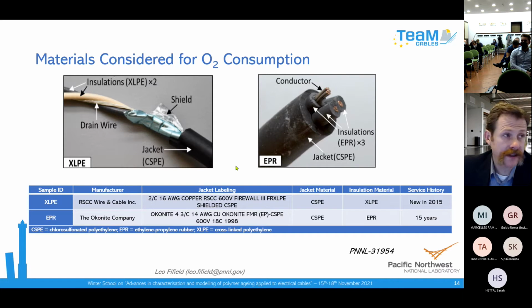In one case we also looked at what we call the dehydrochlorination index, since in chlorinated polymers it's the chlorine leaving that gives a good FTIR signal, compared to the carbonyl index for oxidation. But we haven't done a lot of research with PVC. The problem is that for PVC, conventional non-destructive techniques, including LIRA, couldn't provide extra information about aging, so it's very difficult to follow the aging of these cables.